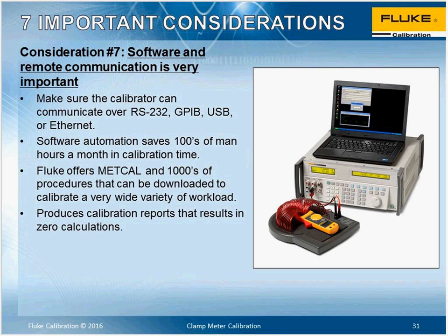Is there some sort of asset management that I could use that would help me manage the products that I'm receiving or even own? And so we offer what we call MetCal, and there are thousands of procedures. Basically you download and load the software, and it's a procedure that is designed based on the manufacturer's specifications. These are highly tested procedures, with all the error calculation, so that the measurement will tell you if it passed or failed. So it simplifies the whole job of calibration tremendously.